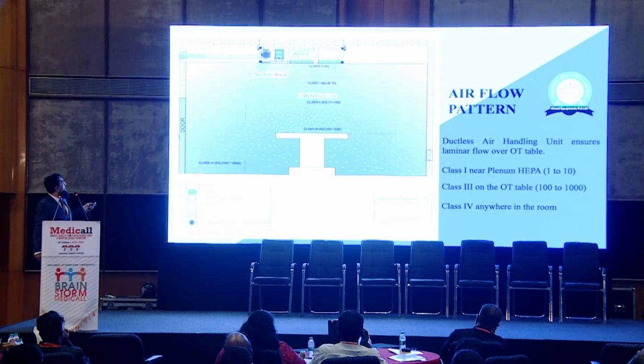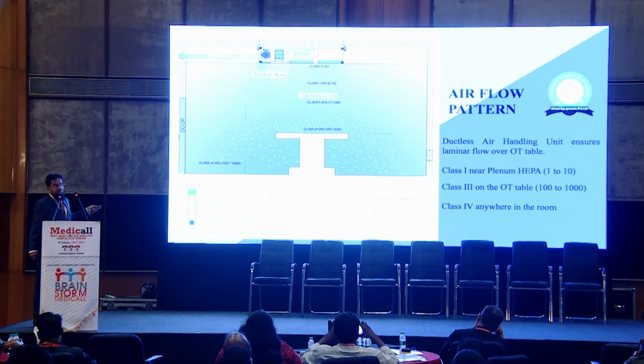Normally the installation is done like this. You have to take 20% fresh air in the first chamber. Here is one of the fresh air dampers. The internal air is also sucked in over here, and both airs get mixed. This is the mixing chamber. In this mixing chamber, we have given negative ionizers and UV lights. Further, we have given a fresh air damper here also. In between is the cooling coil. This is the backward curve fan, sucking the air from the cooling coil through this HEPA. It will come out at table level, but before that there are activated carbon filters also in this area.